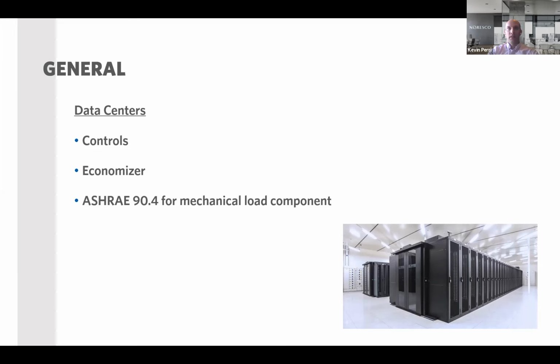Okay, so in general, on the mechanical side of things, they've updated the data centers in the general category. And really what they put in there is an exception. Data centers are now exempt from the requirements in sections 403.4 and 403.5, which I don't expect you to know, but really those are the control section and the economizer section. So if you now have a data center, remember that new definition, they don't have to follow the control section or the economizer section just for that data center portion. So if your building's a complete data center, that's fine, but if you have a portion of your building that's a data center by the new definition, then that portion wouldn't have to follow those two sections. However, the rest of the building still would have to follow that.